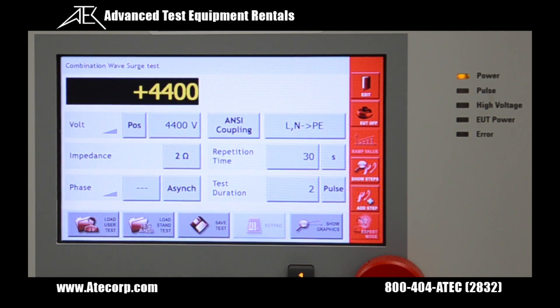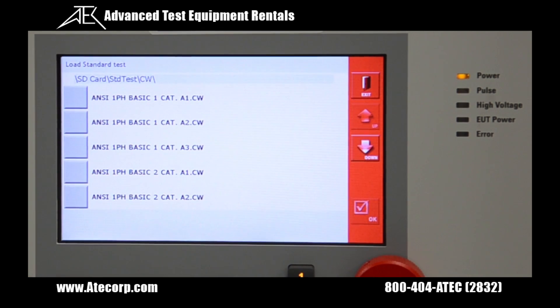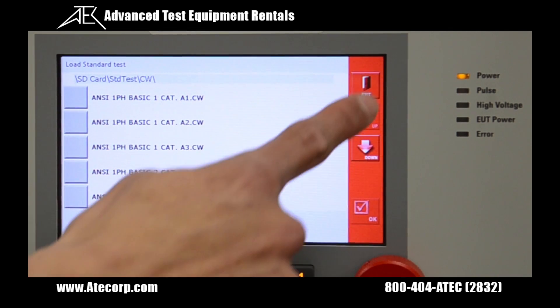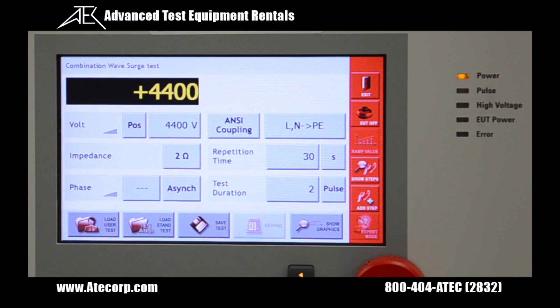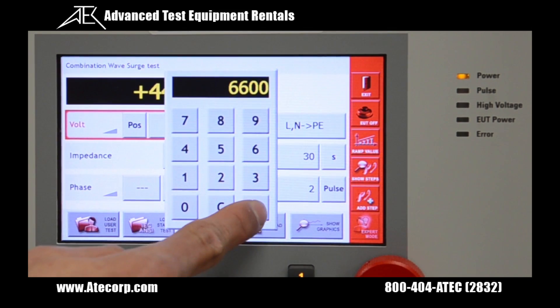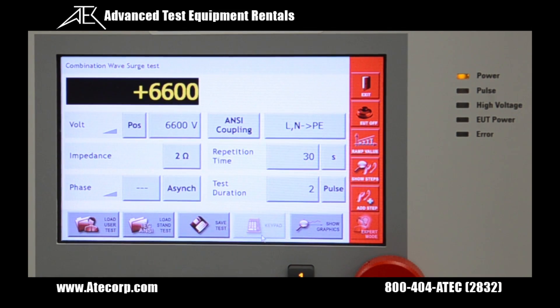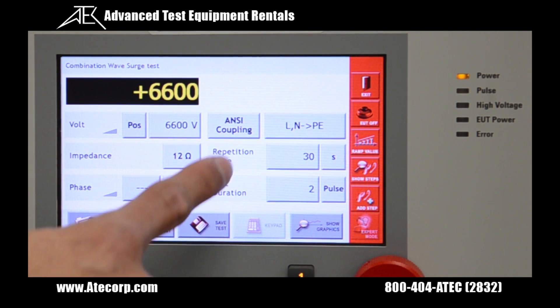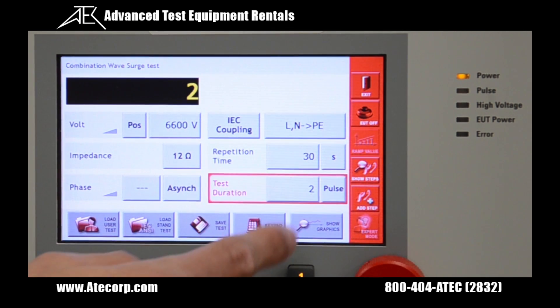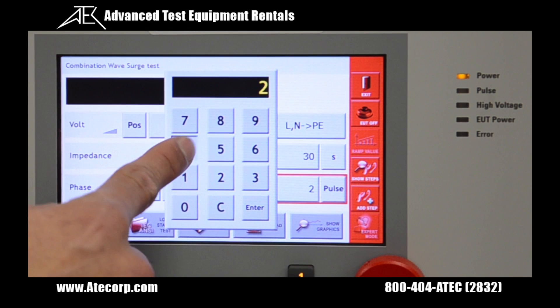From here you can manually change your settings, or you can go into the standards library and pick out one of the predefined standards. For example, let's change the output voltage from 4.4 kV to 6.6, change the impedance from 2 ohms to 12 ohms, leave the phase sync the same, but change from ANSI coupling to IEC coupling.